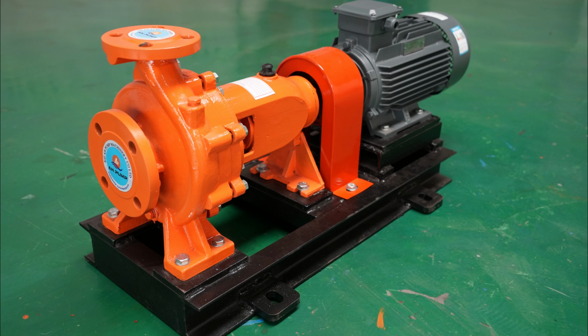That NPSH we talked about earlier, making sure that's adequate can help prevent cavitation. Also, no air in the suction line. That's key too. So NPSH officially on my watch list now. Okay. Other things that cause vibrations. Bearing failure. Yeah. That's another common one. Worn or damaged bearings, they'll create all sorts of racket.